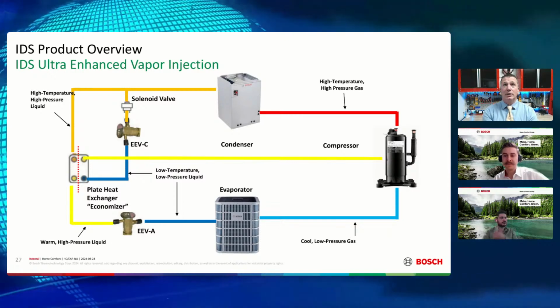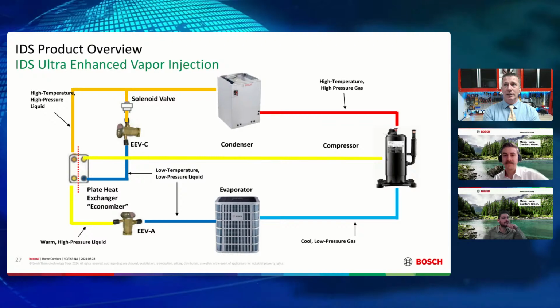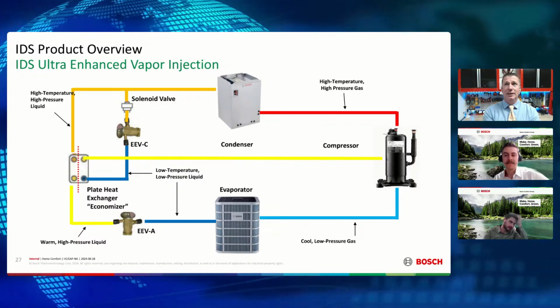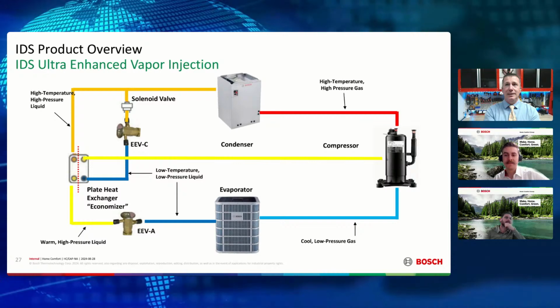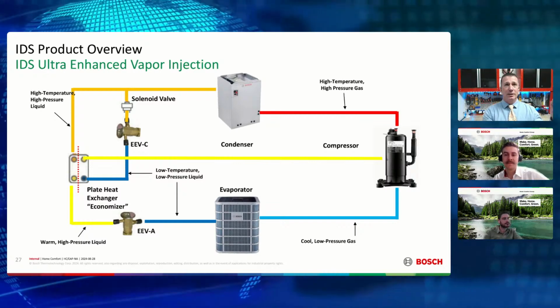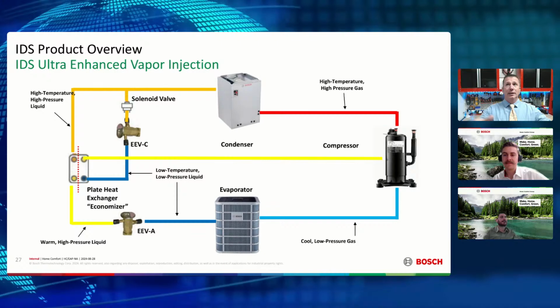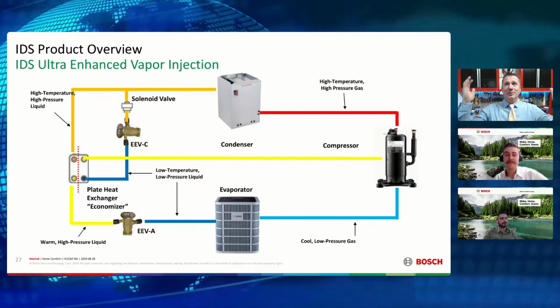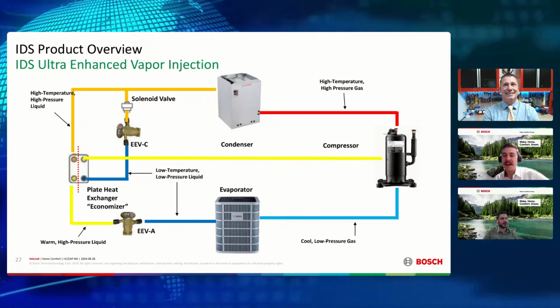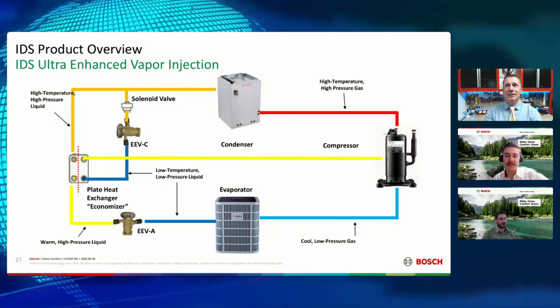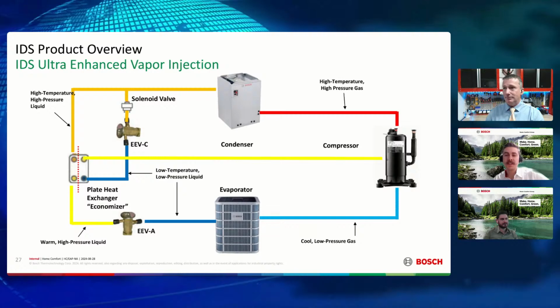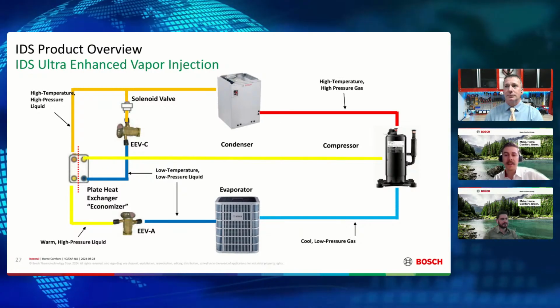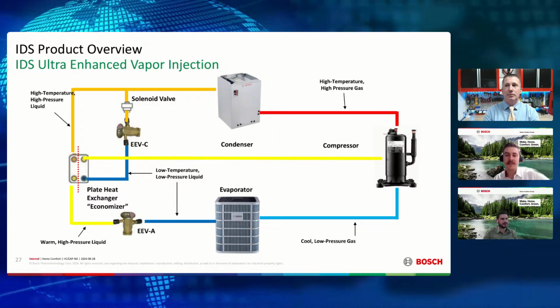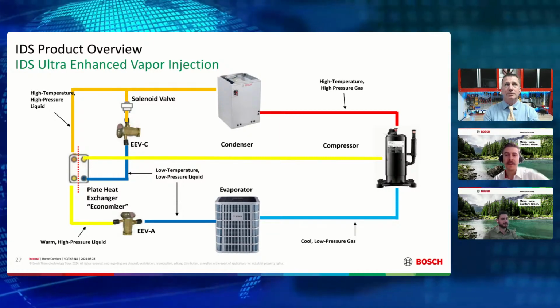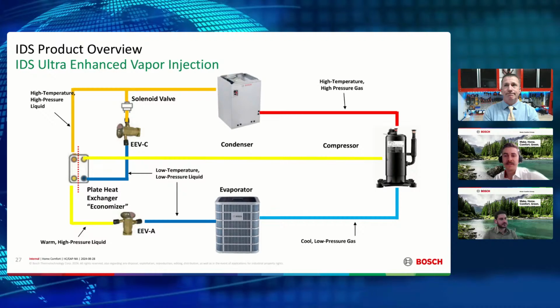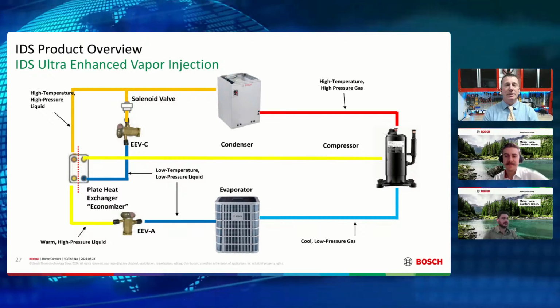And oh, by the way, you're not going to need any electric resistive heating because your heat pump is now capable of your full heating load. So we've conquered heating capacity in the heating mode, and we've conquered dehumidification in the cooling mode, all in one piece. Setup is really important, right? Knowing that function is there and available, and setting it up out of the box when you commission it is critical to getting that level of quality and comfort. It really comes down to understanding the pieces of equipment.